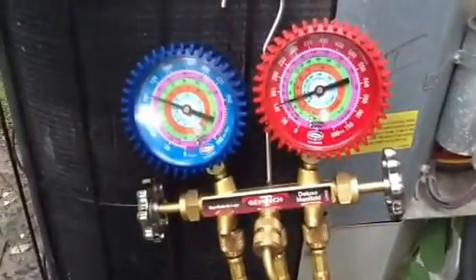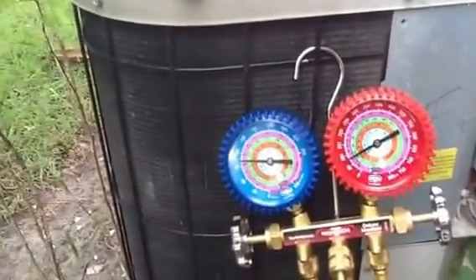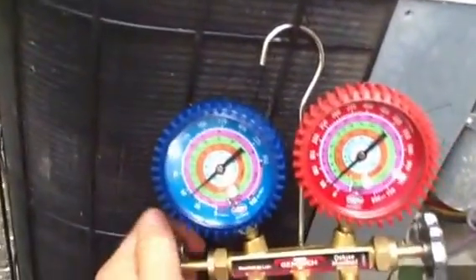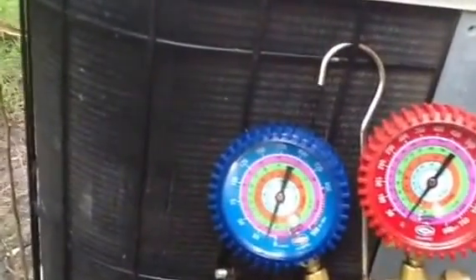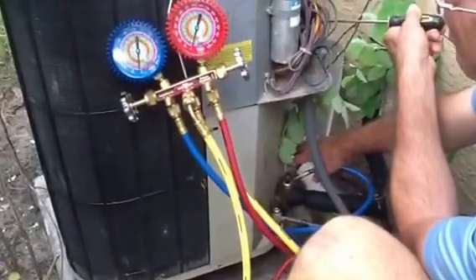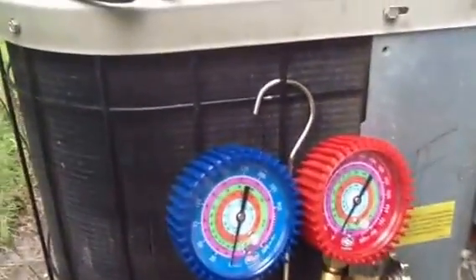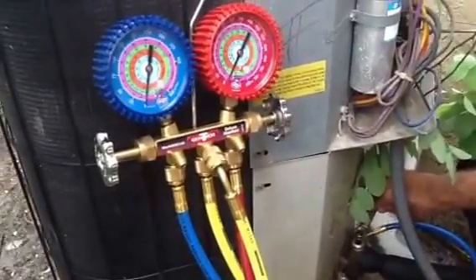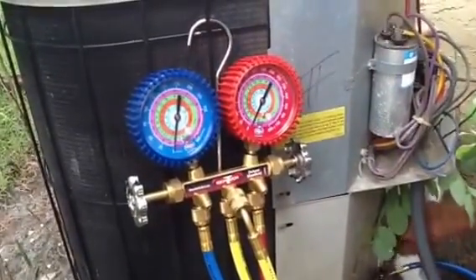Watch the gauges as it goes down to atmospheric pressure. Now I'm going to start torquing down over here on my suction line as it gets closer. See it goes down to zero — it's pumping. These old reciprocal compressors are going to handle a lot more than the scroll compressors. You see my low side gauge is below zero. I'm going to go ahead and pump it on down. Close it off.